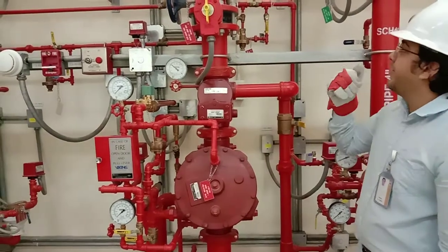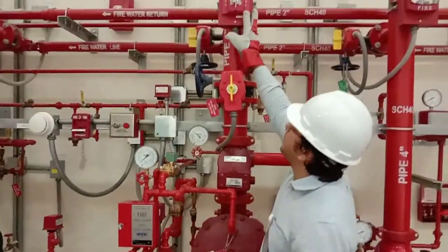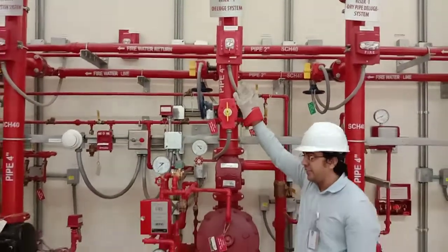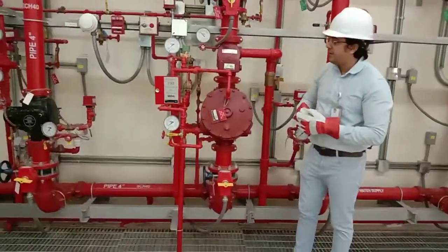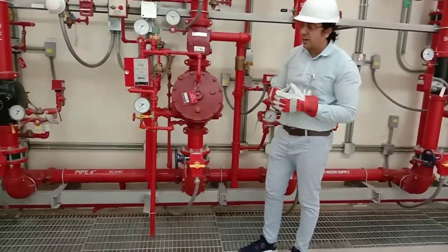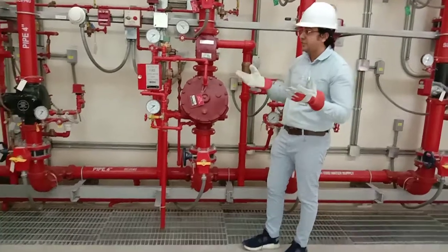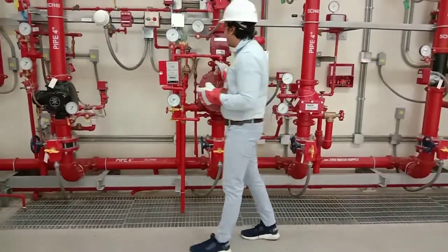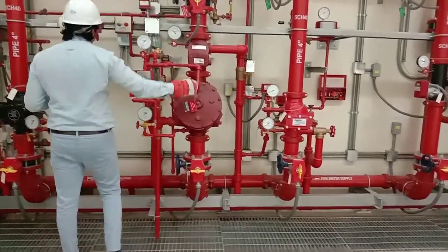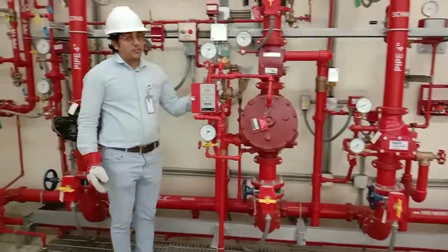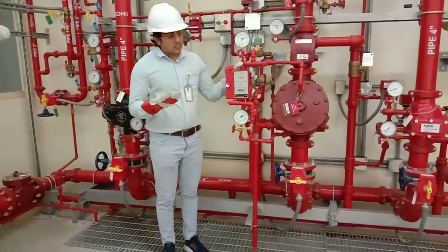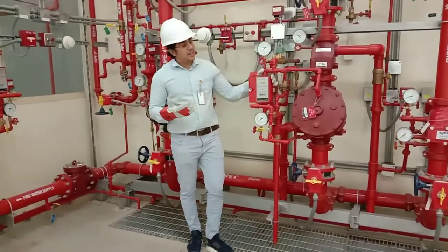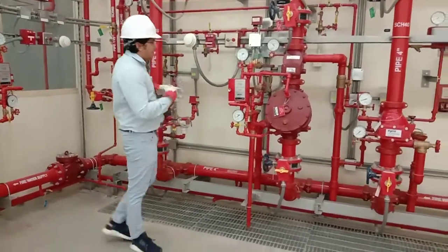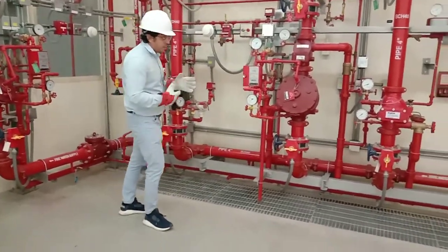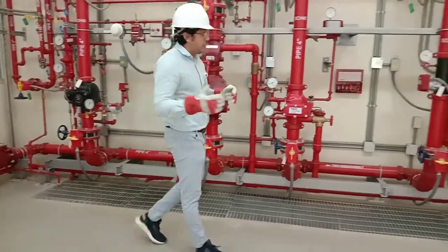Once the system activates, it will give a signal. The flashing light and the strobe will activate, and it will give a signal to the fire alarm panel, and then people will understand there is a fire, and they will try to leave the building. So this is all about the pre-action system. We discussed wet, dry, deluge, and pre-action systems. Now I just want to give a quick summary of all the four risers we discussed today.